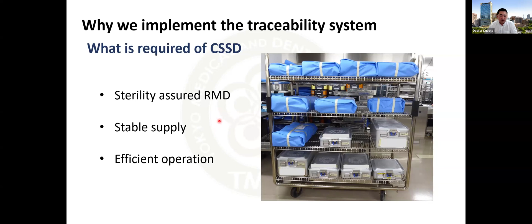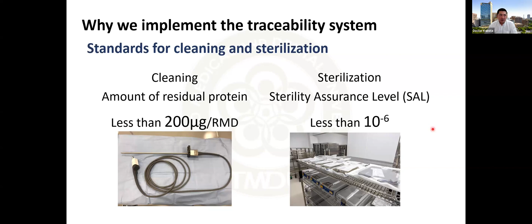There are standards for ensuring the sterility of an instrument. There are standards for cleaning and sterilization. In cleaning, each instrument must be cleaned so that the amount of residual protein is less than 200 micrograms. This is just the Japanese standard, and some countries have stricter standards. For sterilization, there is a sterility assurance level called SAL, which requires that the sterilization condition be achieved to less than 10 to the minus 6. This is a global standard. When this condition is achieved, it's considered to be assured that the instruments are sterile. If I were to explain this standard, I'd end today's webinar with just this discussion, so I'll skip it.